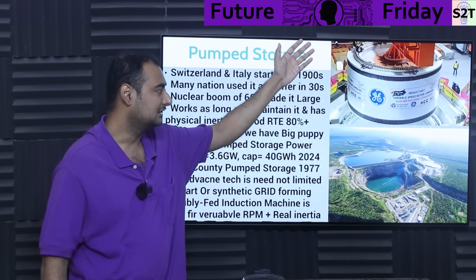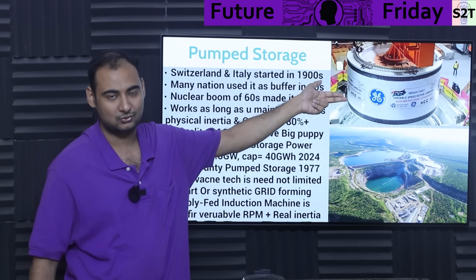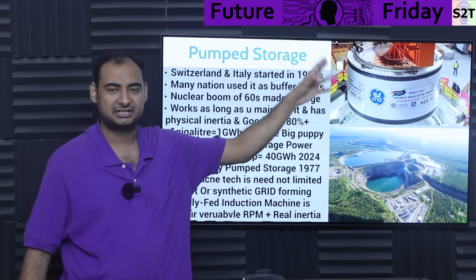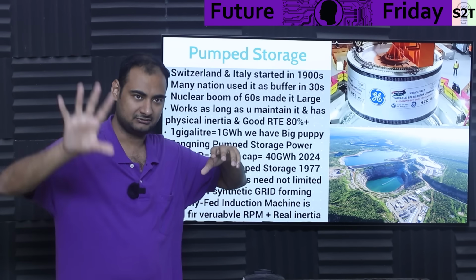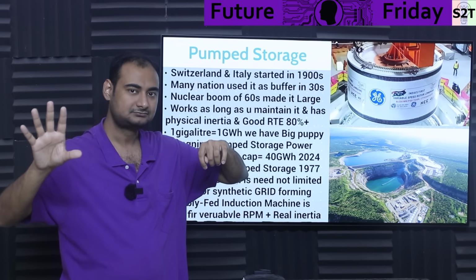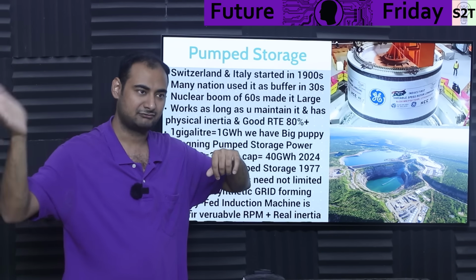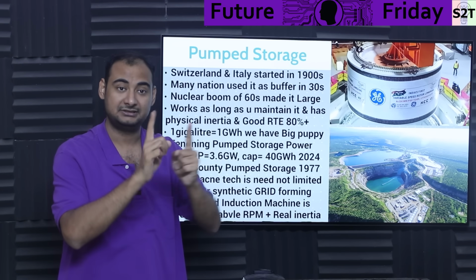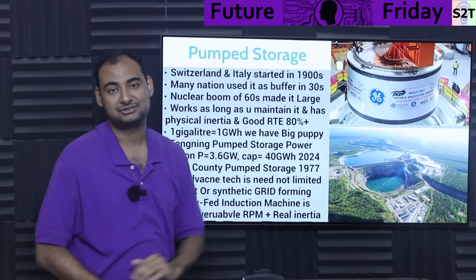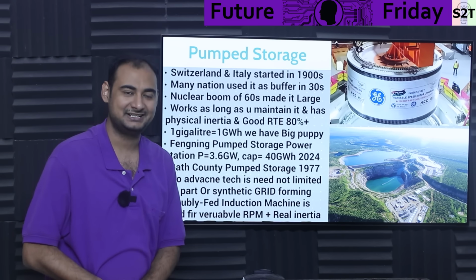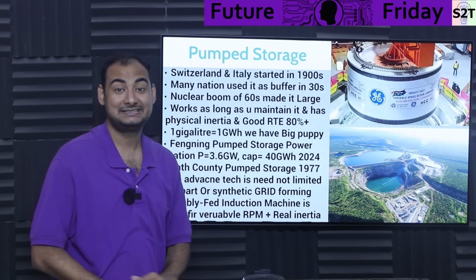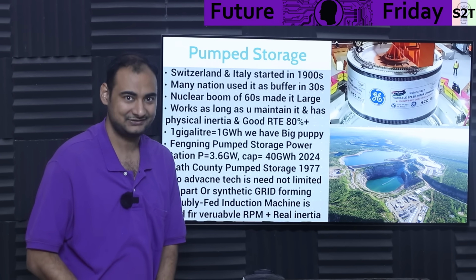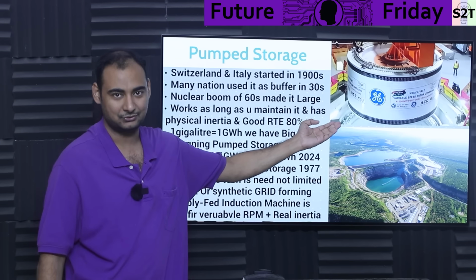Let's say this rotor is 250 megawatt. You control 10 to 30% of the energy, taken out through what we call VFD - basically you convert AC to DC, then DC to AC, and control the slip. That's how you change the rotation while still maintaining synchronization, because the stator didn't change. The stator still behaves exactly as if it has a rotor rotating inside.